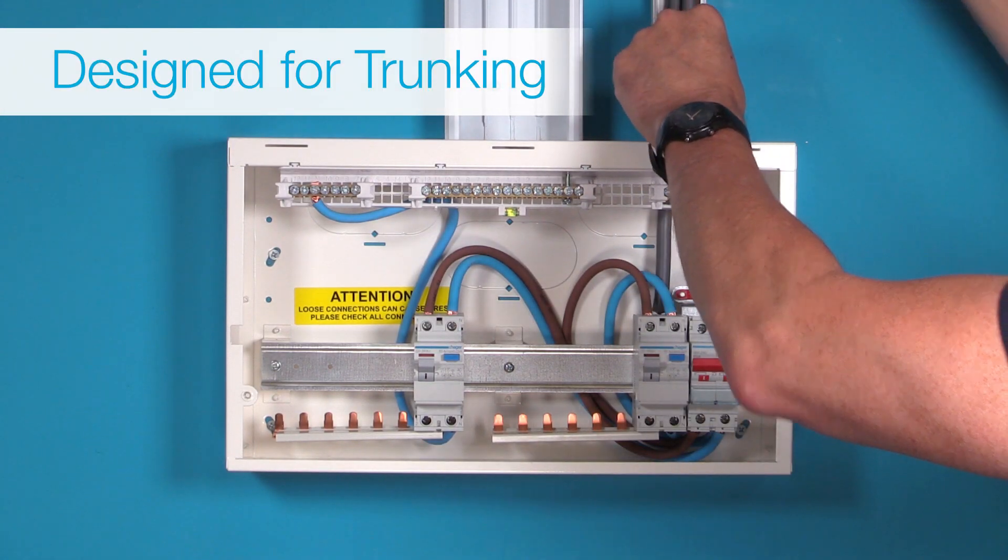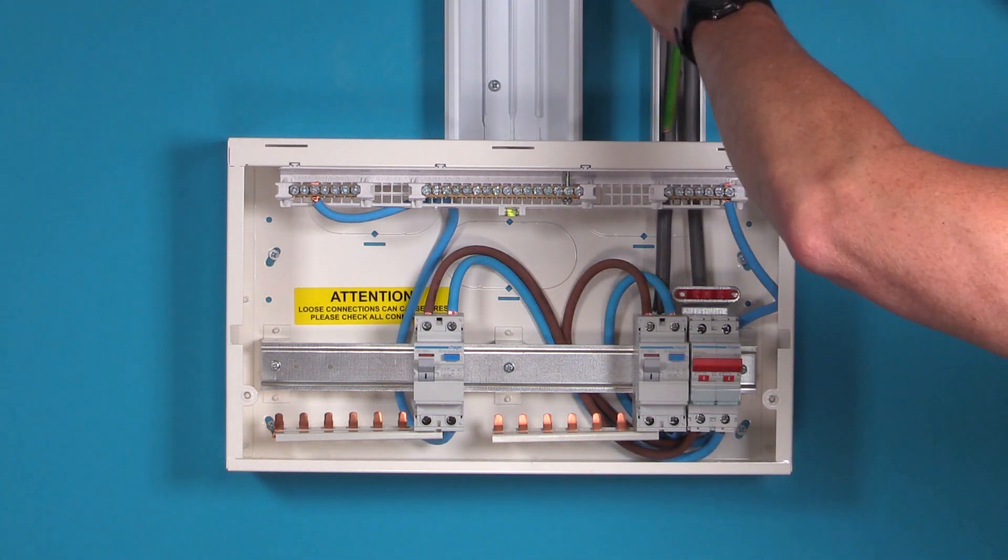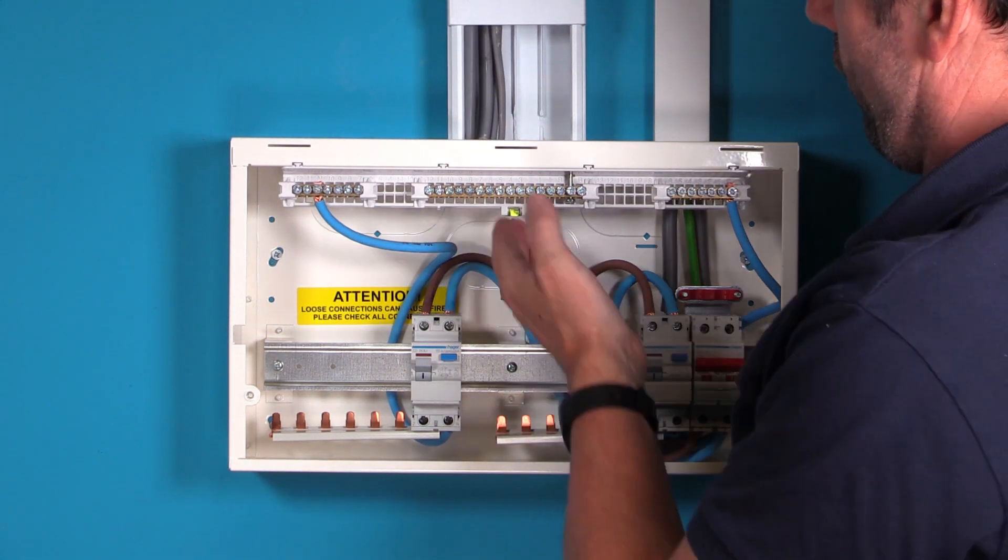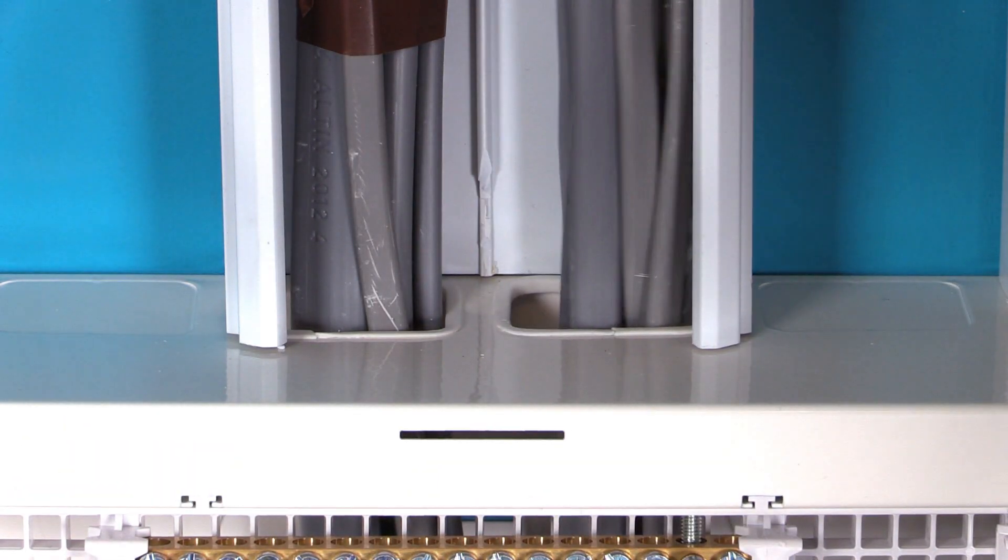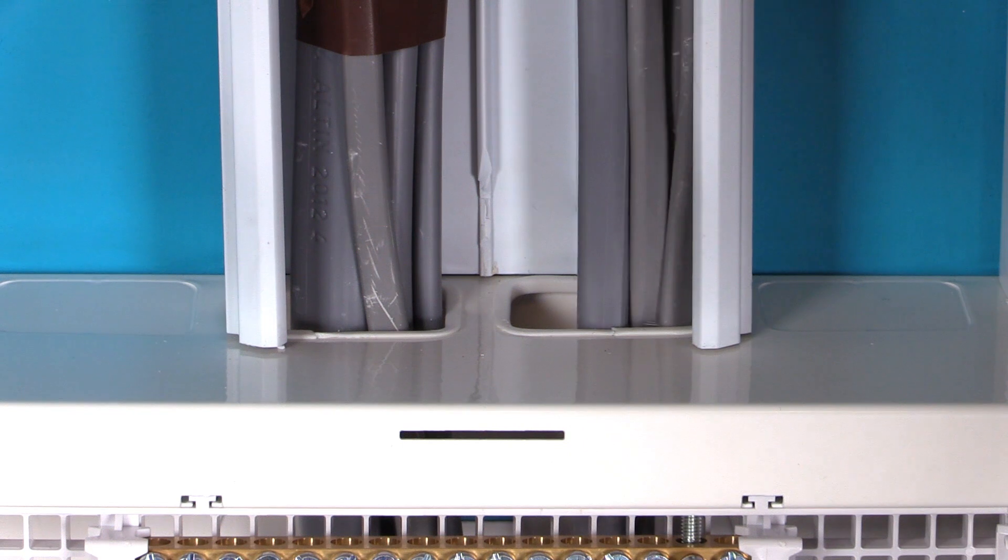In order to maintain the IP4X rating required, we recommend using trunking as our entry points are spaced to fit standard sizes. Using plastic trunking will not affect your compliance to Amendment 3 of the wiring regulations.